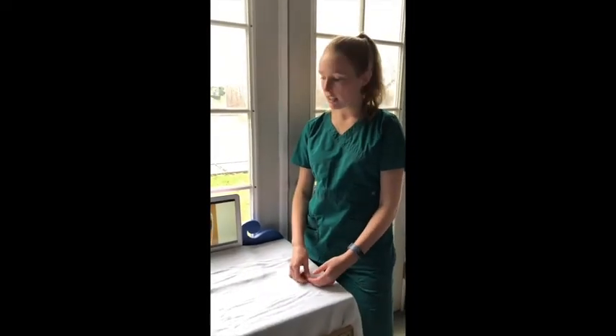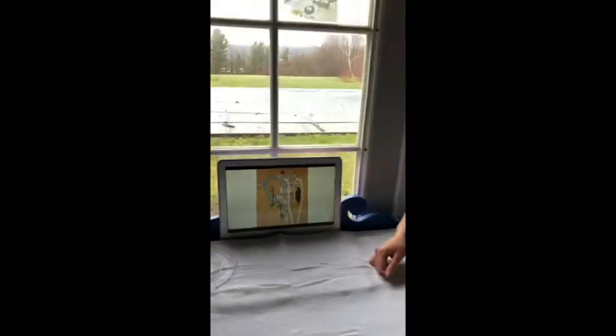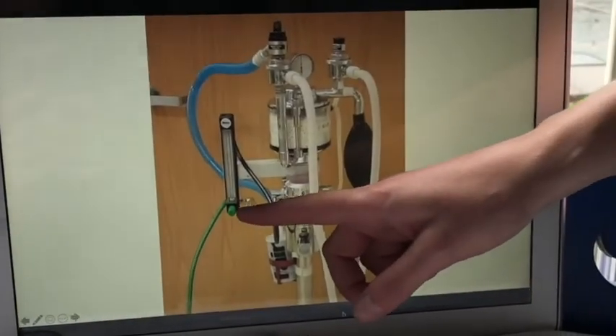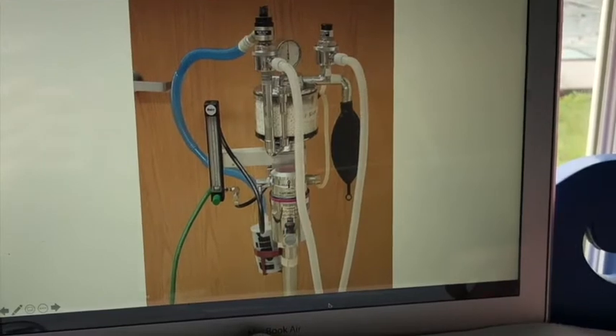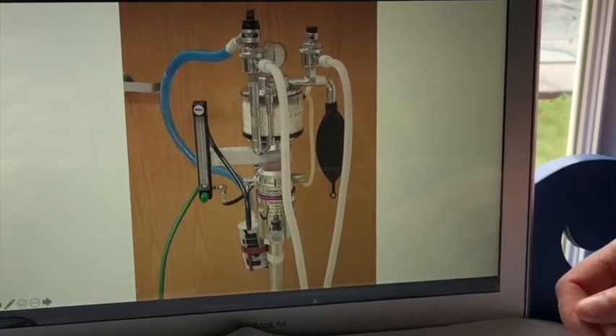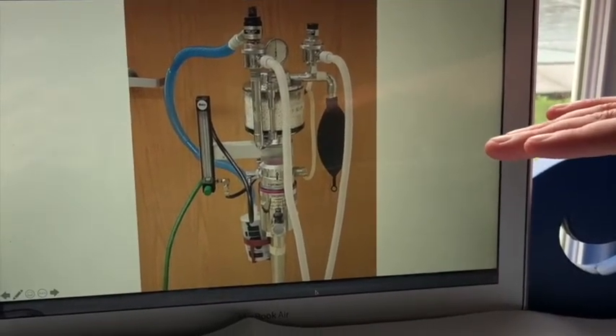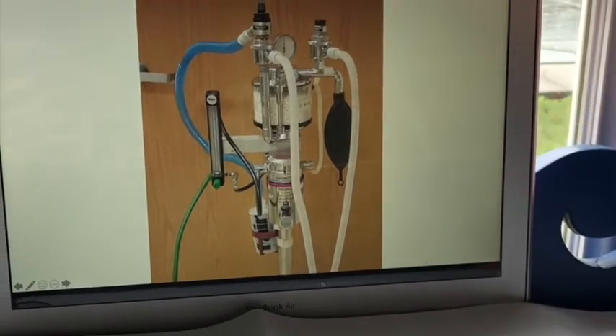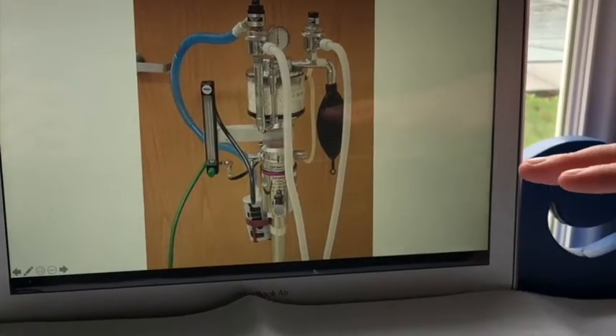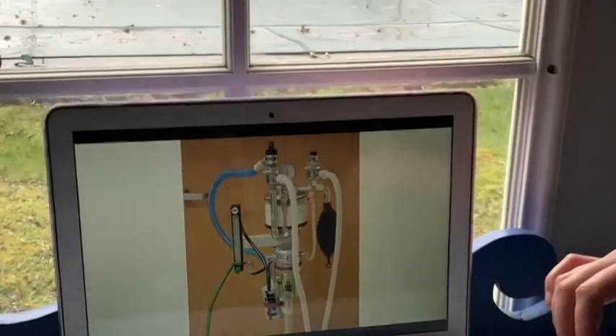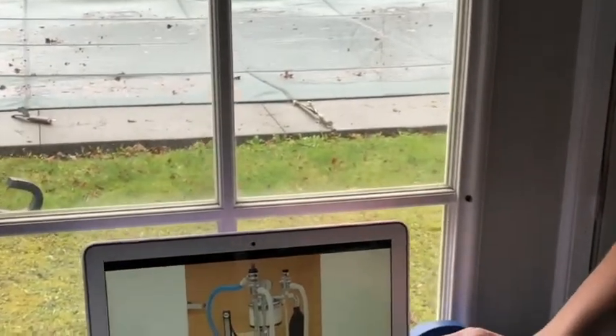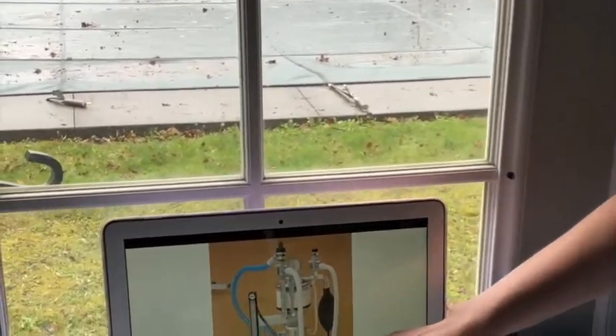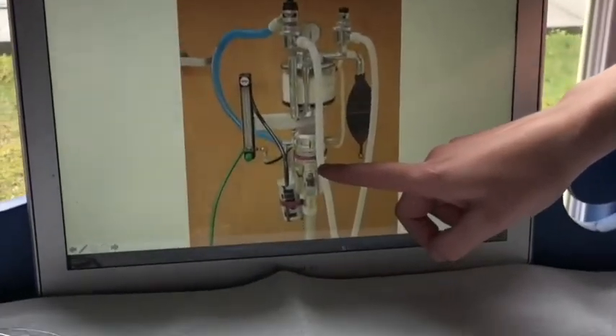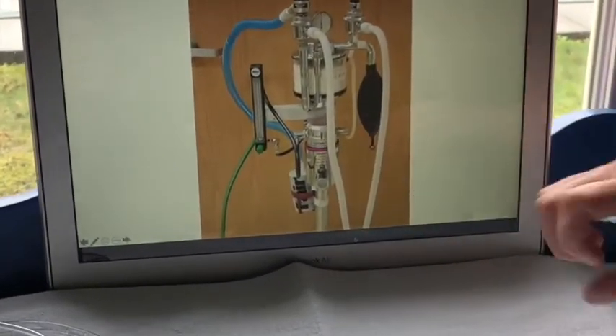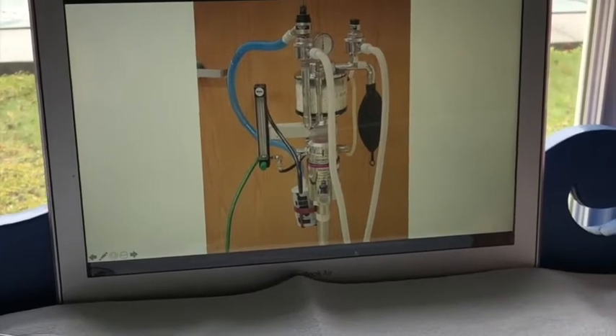Okay, so now we're at our anesthesia machine. We need to make sure that's all ready to go. So the first step is to check our flow meter. So we're going to turn this green knob up to 1.5 liters per minute. Make sure the knob turns smoothly. It stays at that 1.5 liters per minute. And then when we turn it off, it goes back down to 0, nice and easy. The next part is to check our vaporizer. We need to make sure that is full or has appropriate level of anesthetic in it, and that it's also nice and tight and all together.